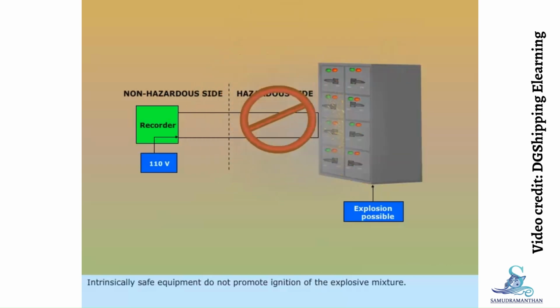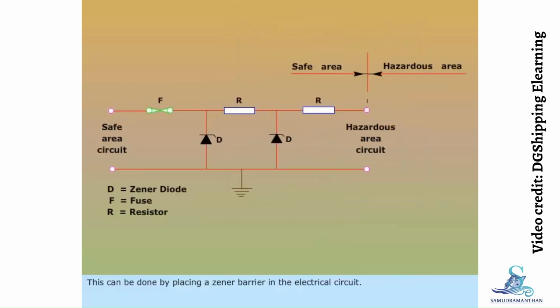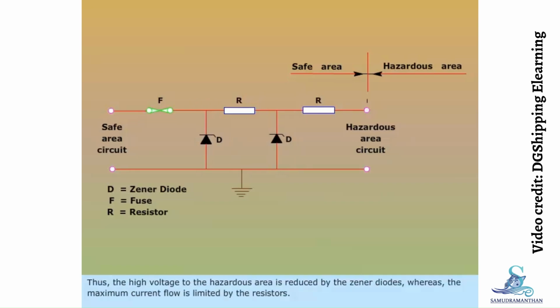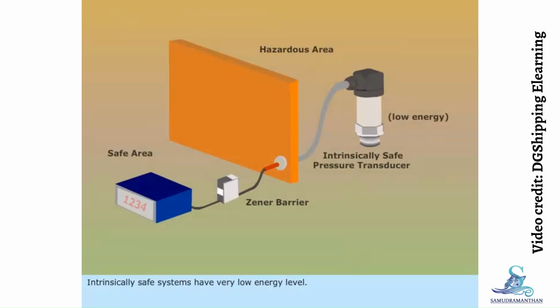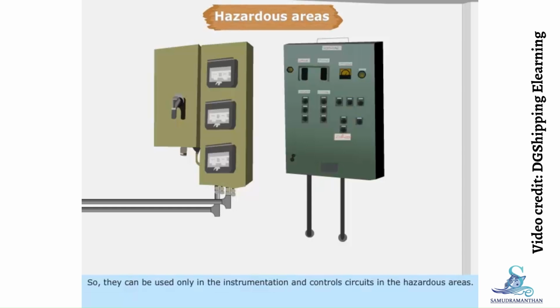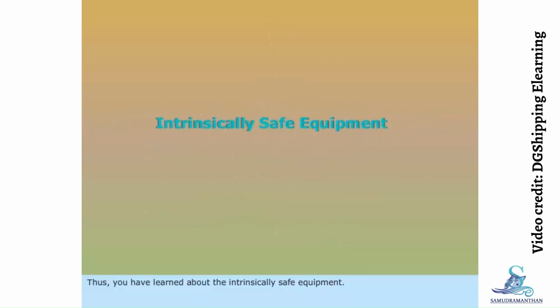Intrinsically safe equipment does not promote ignition of the explosive mixture. This can be done by placing a Zener barrier in the electrical circuit. Thus, the high voltage to the hazardous area is reduced by the Zener diodes, whereas the maximum current flow is limited by the resistors. Intrinsically safe systems have a very low energy level, so they can be used only in the instrumentation and control circuits in the hazardous areas. Thus, you have learned about the intrinsically safe equipment.